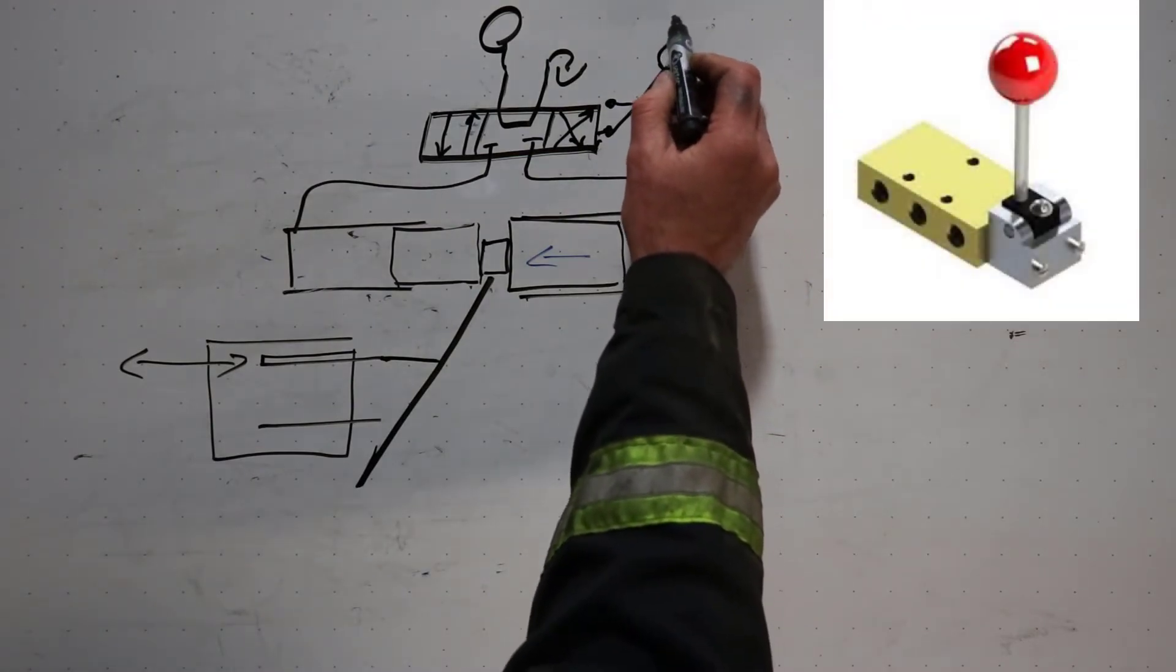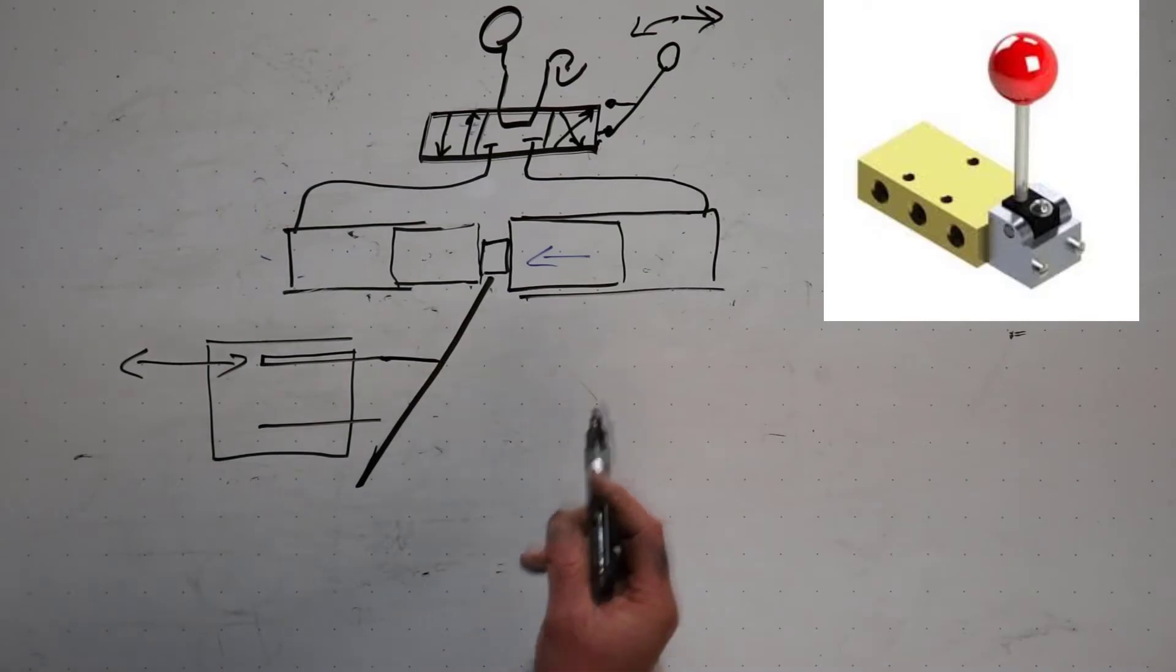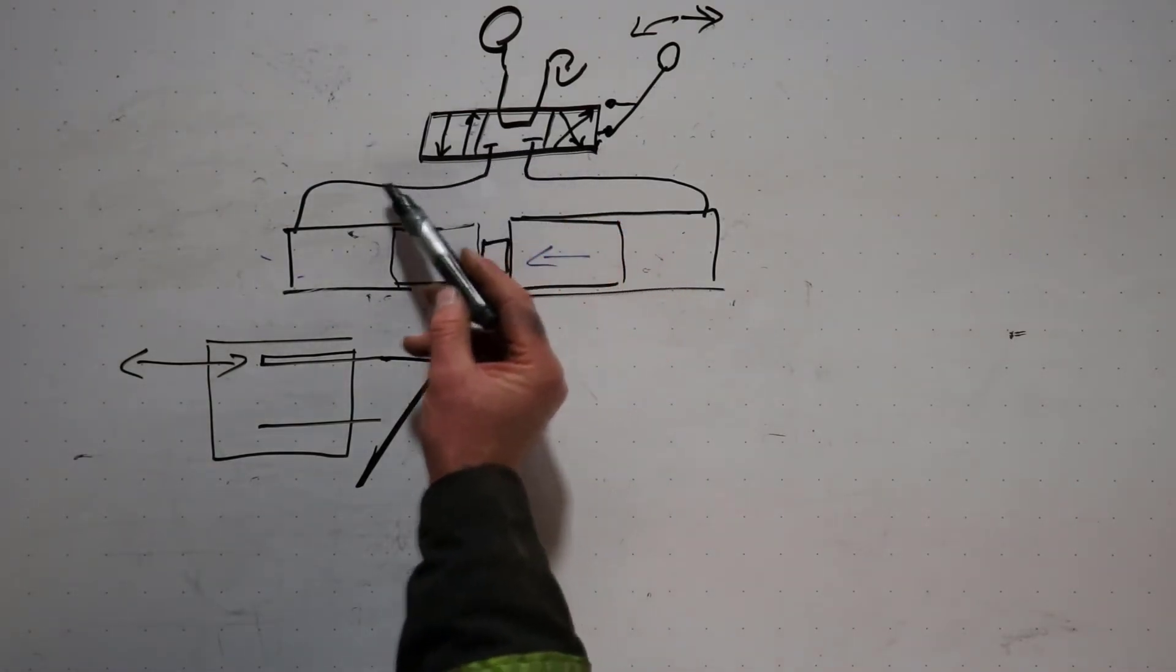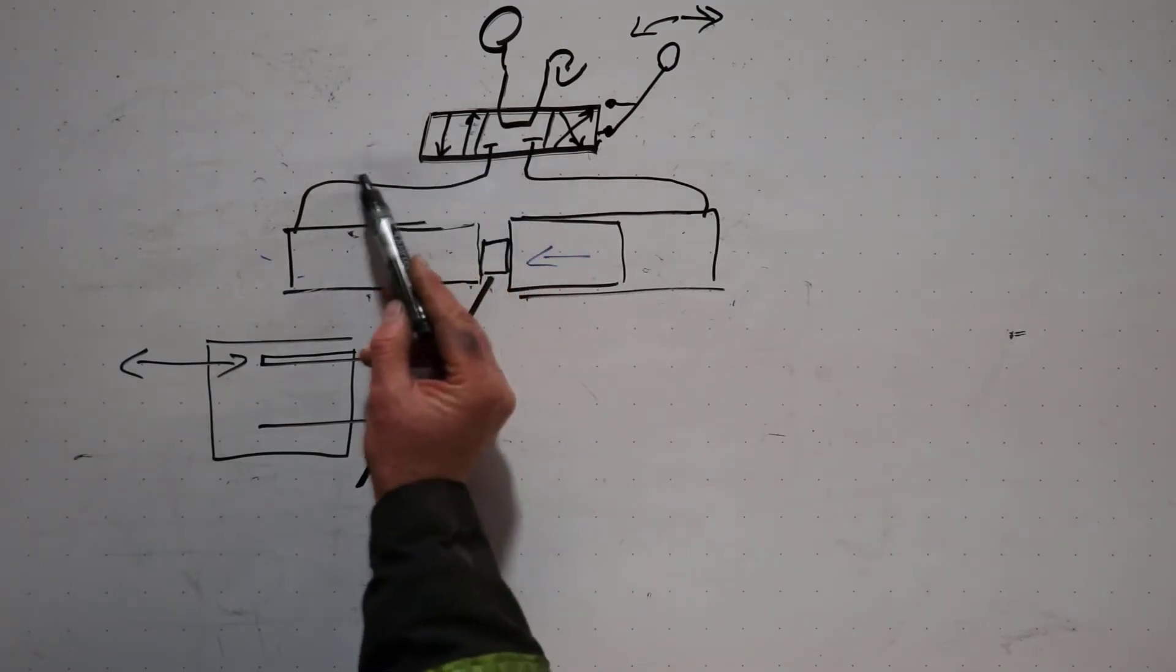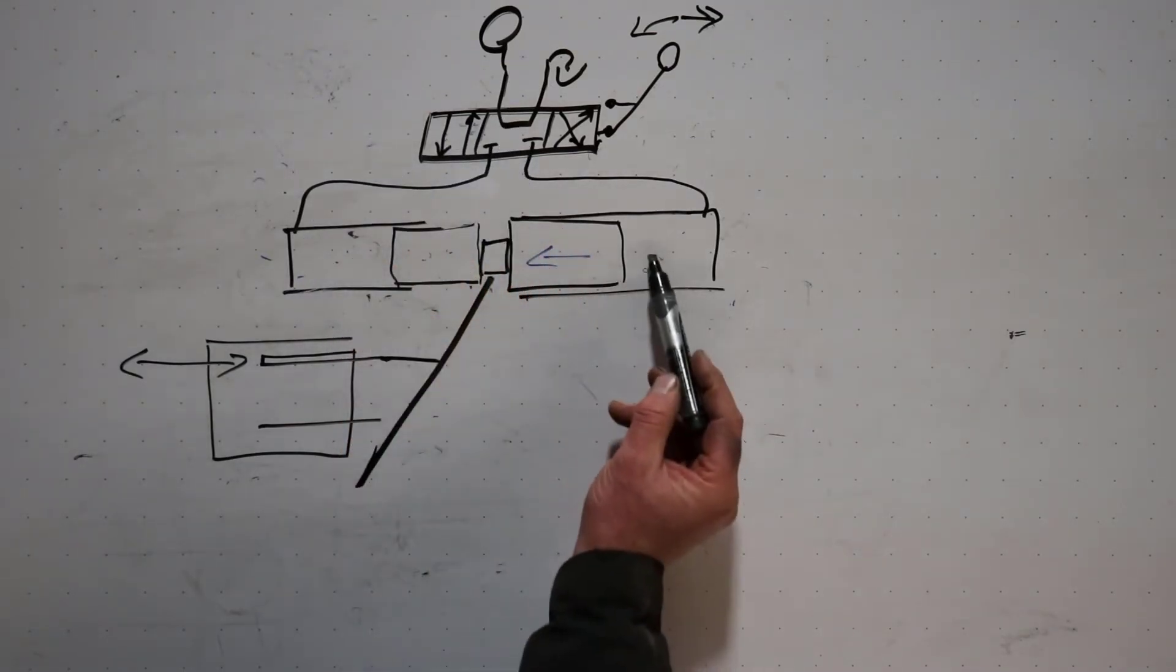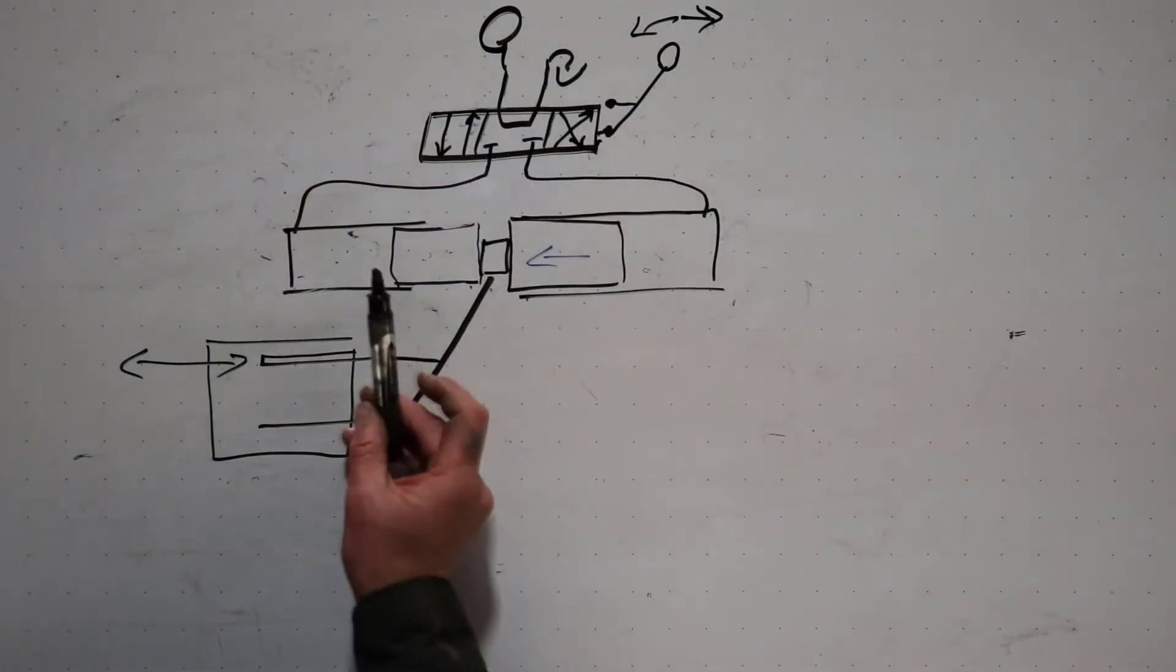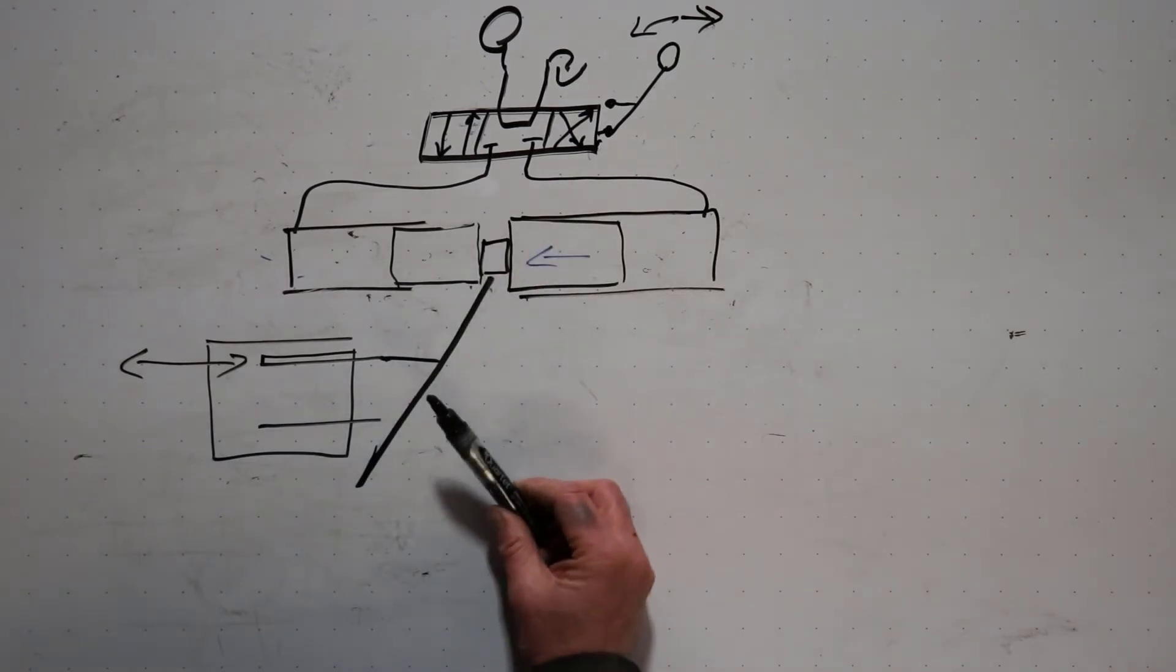So now when I move this lever forwards and backwards, I can open and close the control valve and send oil into this side. If I put this spool here in line, the oil's gonna flow through, flow into here. This side is hooked to tank, it goes through there, and the cylinder will move to the right, moving the pump to maximum displacement.